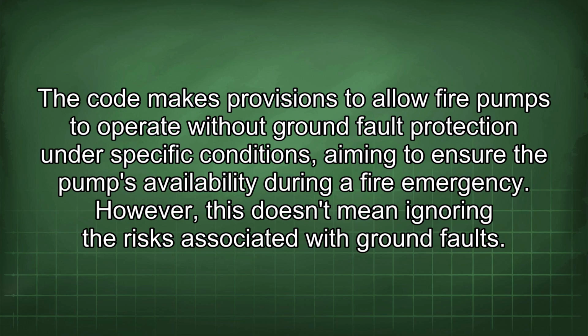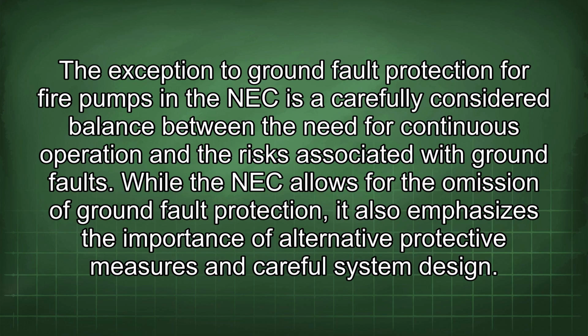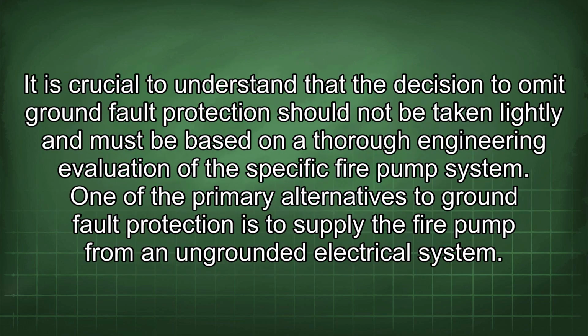However, this doesn't mean ignoring the risks associated with ground faults. The exception to ground fault protection for fire pumps in the NEC is a carefully considered balance between the need for continuous operation and the risks associated with ground faults. While the NEC allows for the omission of ground fault protection, it also emphasizes the importance of alternative protective measures and careful system design. It is crucial to understand that the decision to omit ground fault protection should not be taken lightly and must be based on a thorough engineering evaluation of the specific fire pump system.